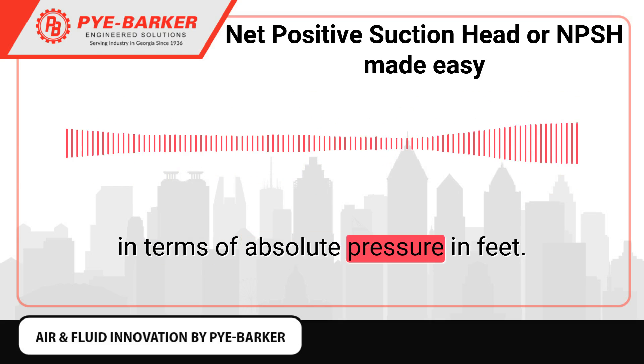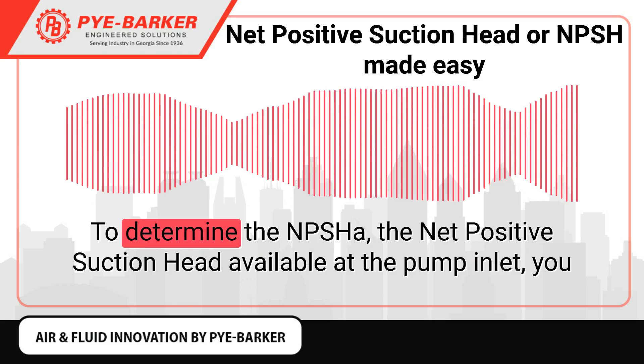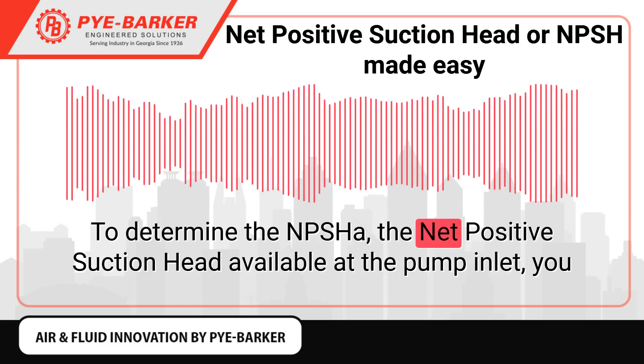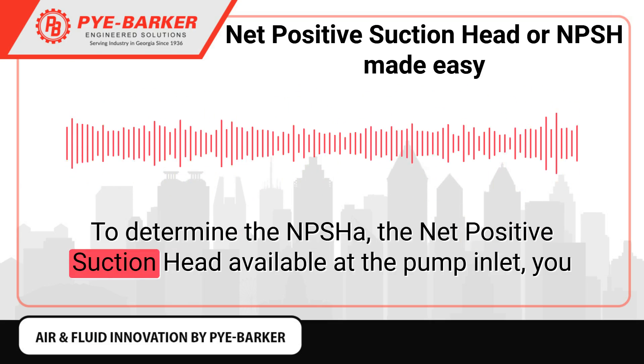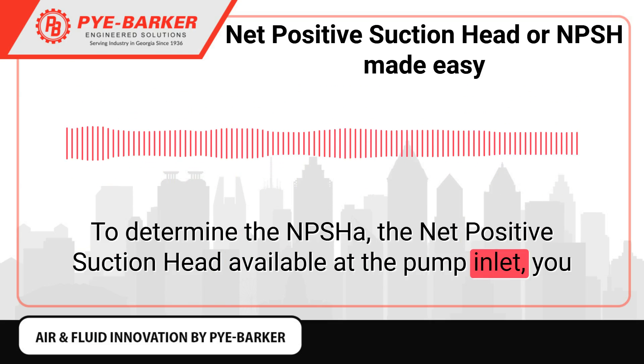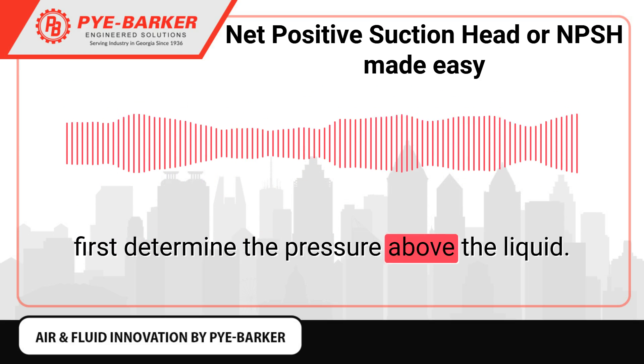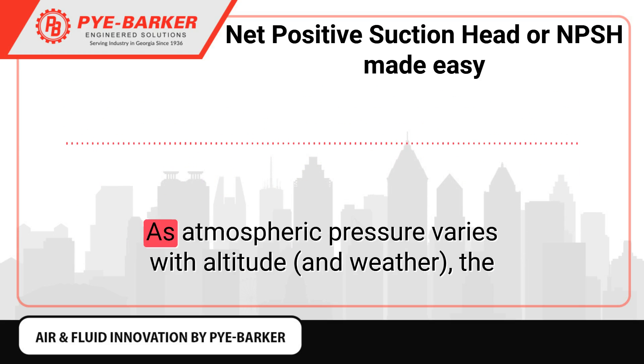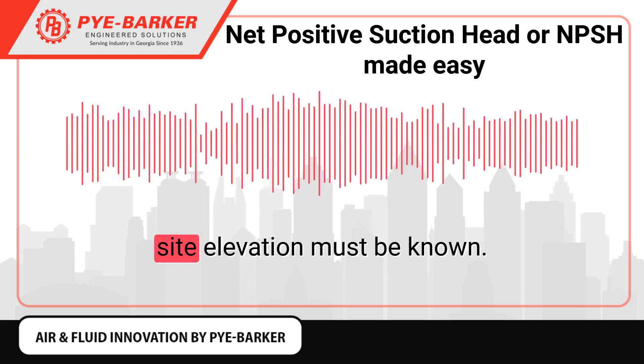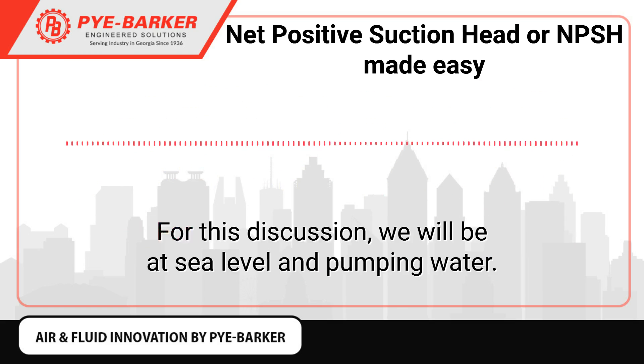For a basic understanding of Net Positive Suction Head, you must think in terms of absolute pressure in feet. To determine the NPSHA — the Net Positive Suction Head Available at the pump inlet — you first determine the pressure above the liquid. As atmospheric pressure varies with altitude, the site elevation must be known.